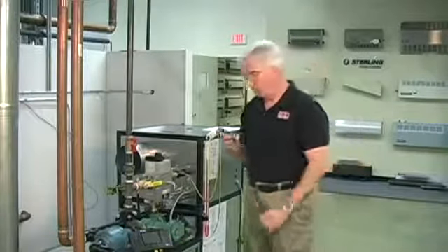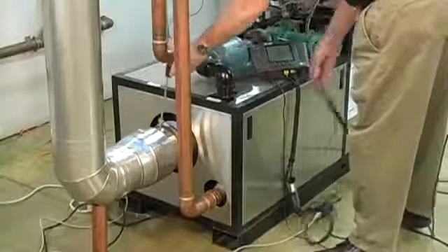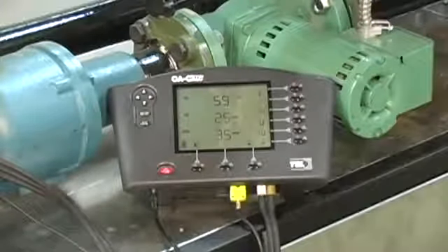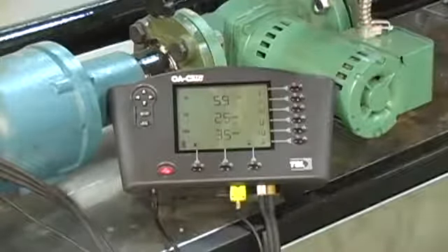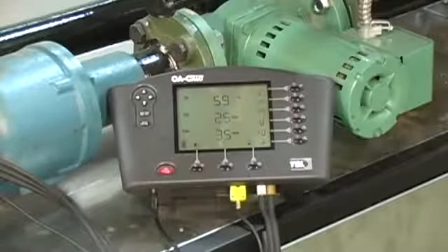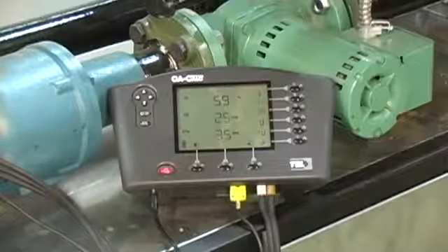We're going to take our test wand and insert it into the test hole in the unit down here at the back. When we're taking our combustion sample, we have to be cognizant of the values that we're expecting to see on this particular unit. If you refer to your installation and operations manual, you'll find some tables in there that identify your low fire combustion and high fire combustion.